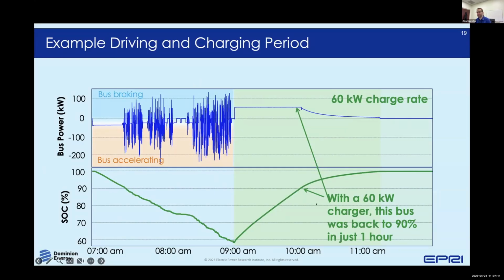But as noted, this probably wasn't the best design from a cost-effectiveness standpoint if charging speed was the only consideration, because within an hour they got back up to 90%. They didn't consume much, starting at 100% and dropping only to 60%. So there was additional room within that range for this particular route. Within an hour they were completely back, leaving several hours of slack time even if they ran the same route again in the afternoon. So that might have been needlessly quick for this application, and it's a good example to help you ask: is it necessary to install DC fast chargers for every bus?